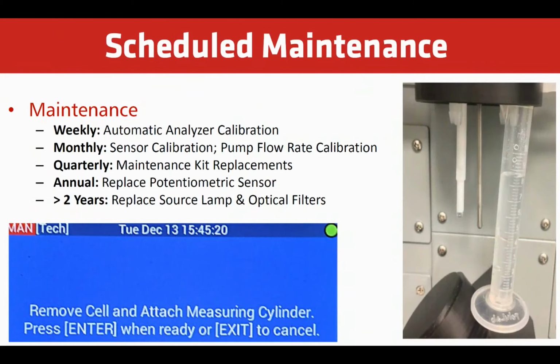So here we're talking about the standard preventive maintenance or scheduled maintenance. Weekly, they're typically set up for an automatic analyzer calibration, so you want to make sure that you have fresh standard available at the analyzer prior to this happening. Monthly, we can do sensor calibration. What we mean by that would be either the pH probes, if it's a titrator, or an ISE probe. We want to make sure that those are within calibration by putting a standard underneath them. We also want to check the pump flow rate calibration, make sure that the pumps are delivering the reagent amounts correctly, not too much or not too little.